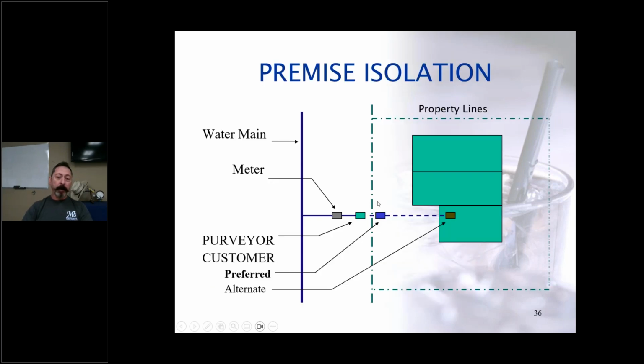Premise isolation, the location of the backflow preventer: if this is a bird's eye view looking down, you have your distribution system service connection into the property line of a building. We could put the backflow preventer just inside the property line, let's say, to isolate the entire property. Or often it's installed inside the building, which is easier for protection from freezing. It's not a confined space if it's in there, and it's more accessible for testing and maintenance and that sort of thing. So often different municipalities or different water purveyors will decide on where this goes. Maybe it's either or. In some cases it can fluctuate based on the property, but that's one method of isolating.